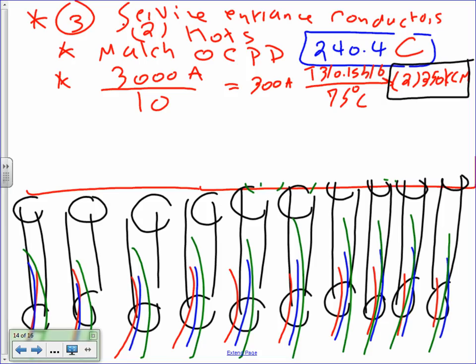Okay. So everybody can see these conduits that you can find here. These are 10 conduits. Each one of them has 3 conductors. Each conductor, guys, has a size of what? Each conductor has a size of 350 kcmil. What insulation, since these will be underground, probably, you're talking about THHW insulation. THHW insulation.